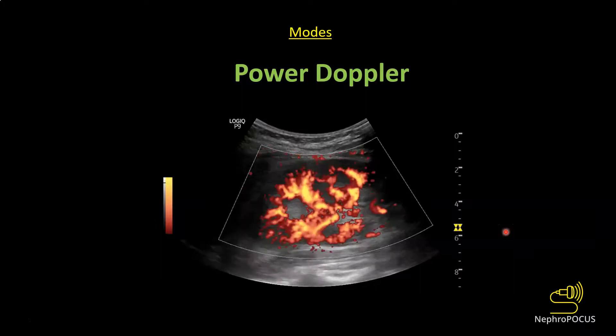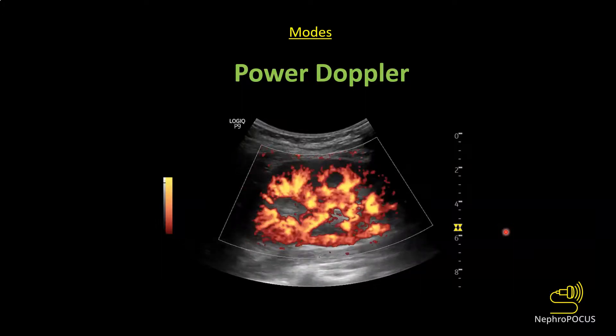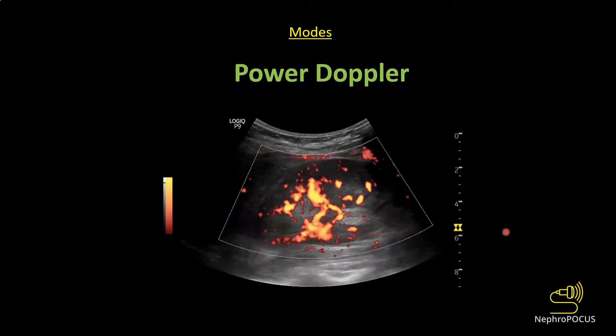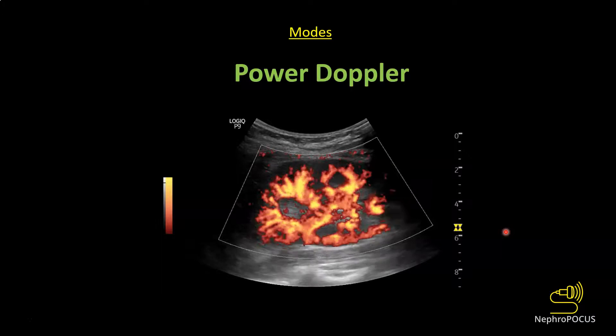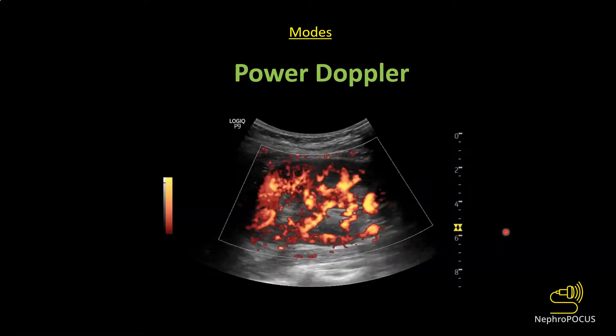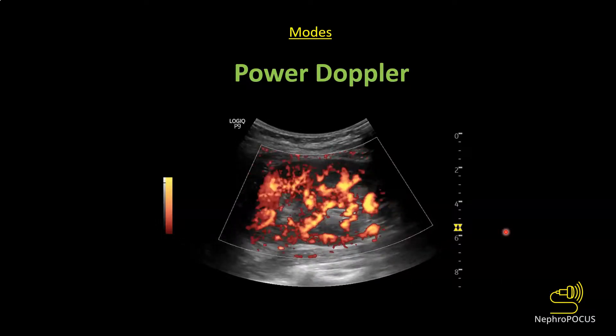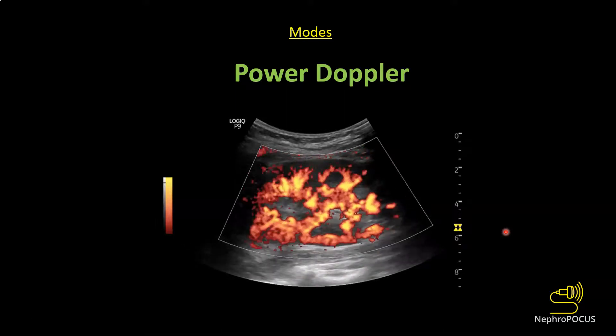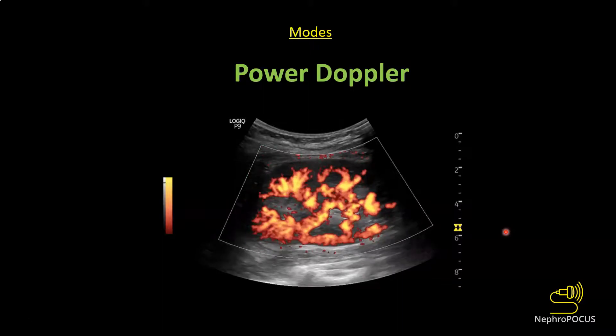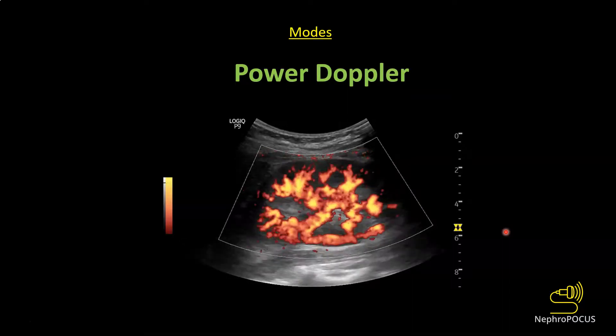Power Doppler is similar to color Doppler in that it represents flow and detects whether blood flow is present. However, instead of using frequency information it uses the intensity of the returning signal, and unlike color Doppler it does not indicate the direction of flow — there is no red and blue, just one color of varying intensity. The advantage is that it can detect low-flow states, such as when draining an abscess or when color Doppler pickup of kidney flow is poor.